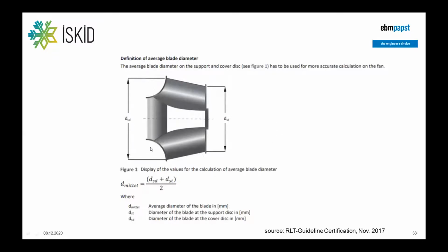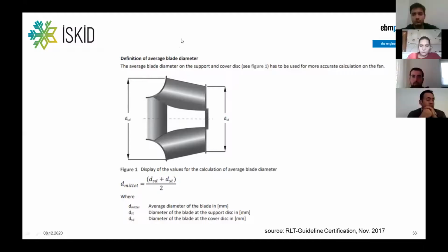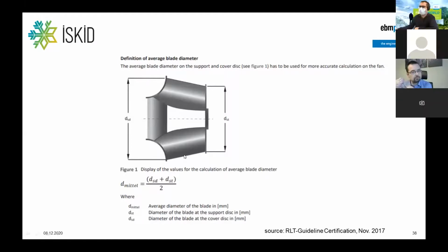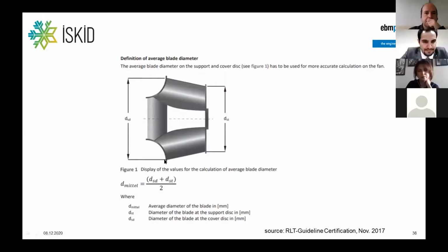And first of all, it's necessary to define the dimension of the impeller. Impeller diameter is necessary when judging the effect of the distance to the wall in the unit, and it's also relevant to calculate the dynamic pressure, because the dynamic pressure is related to the section of the fan outlet. So the definition of the diameter is the mean between the maximum diameter and the minimum diameter, because nowadays the impellers tend to have inclined blades, three-dimensional blades, and therefore it needs a formula to have a common understanding.